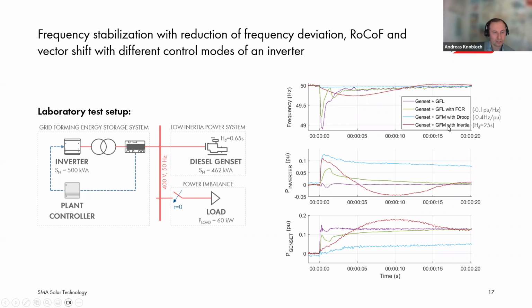And the last response is grid forming control with inertia. And we see again there is an instantaneous response, an instantaneous absorption of power. But according to our inertia constant, as is adjusted afterwards, the inverter tries to reduce the power to the previous set point value in that case. And the rest is taken over by the synchronous generator that somehow interacts with the inertia, with the inverter system. But nevertheless, it is capable to reduce the rate of change of frequency significantly and also the nadir compared to the grid following cases. And this shows us also the value that we obtain from the different grid forming control behaviors. Yeah, that's the difference.